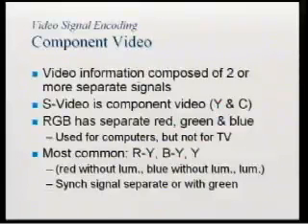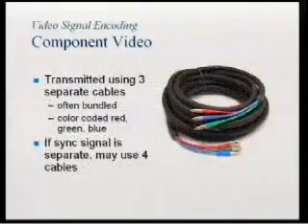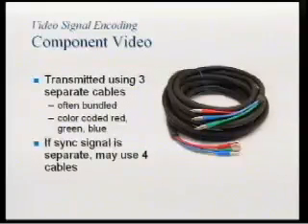Some monitors also have a separate cable that just transmits the synchronization signal. And again, this is a cable like you might use at home to connect your DVD player to the back of your TV. It's got 3 different cables. They're labeled red, green, and blue. And the one you use in the operating room is probably going to look like this, but it's going to have a 4th cable for the synchronization.